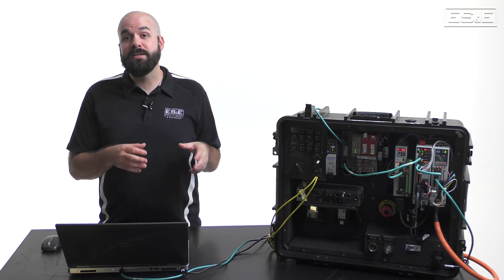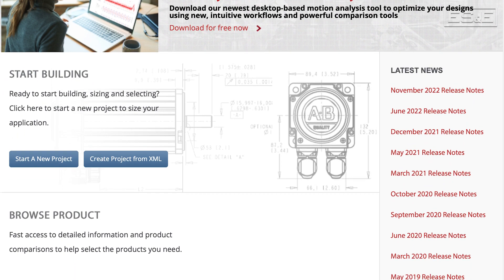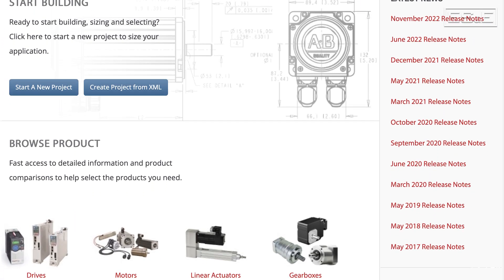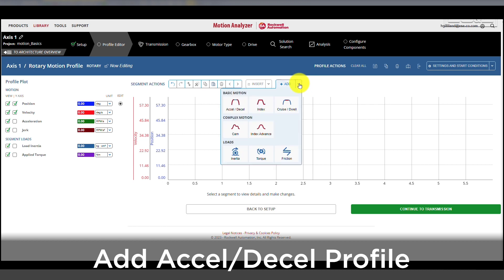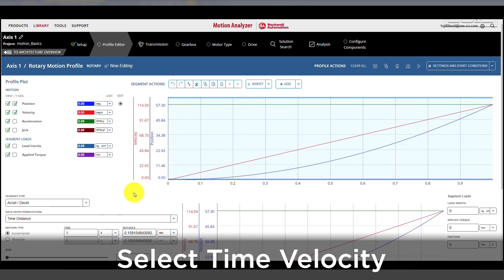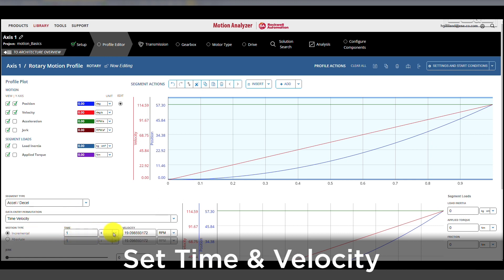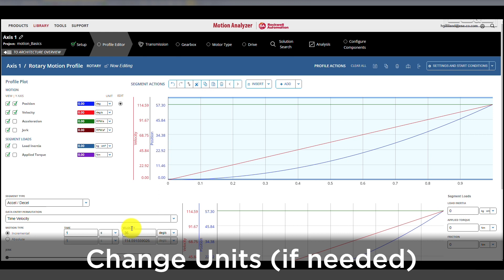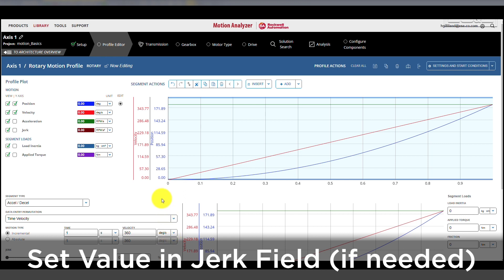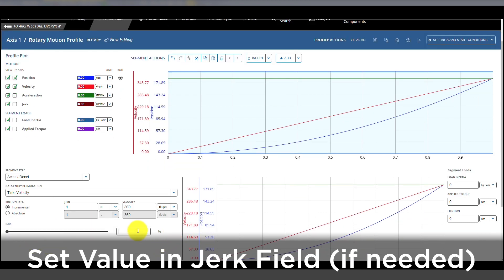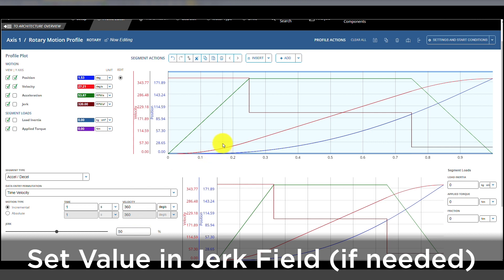Now let's discuss how to define the dynamics of the move. Using a tool like Motion Analyzer Online is helpful here — there's a link to this free tool in the description below. For this example I would like to run the servo at 360 degrees per second and reach full speed in exactly one second. Using an Accel/Decel profile I can generate the information I need. Add the Accel/Decel profile, then select Time Velocity for the data entry permutation. This allows us to enter a time of 1 second and a speed of 360 degrees per second.